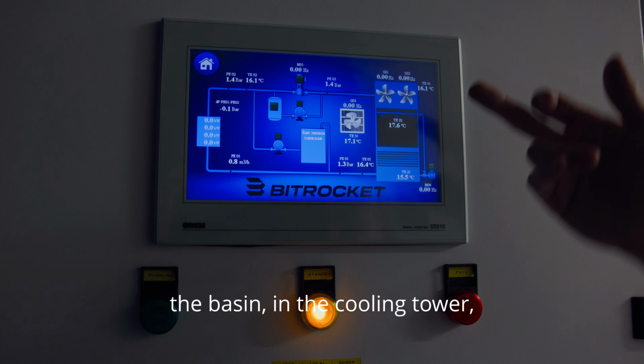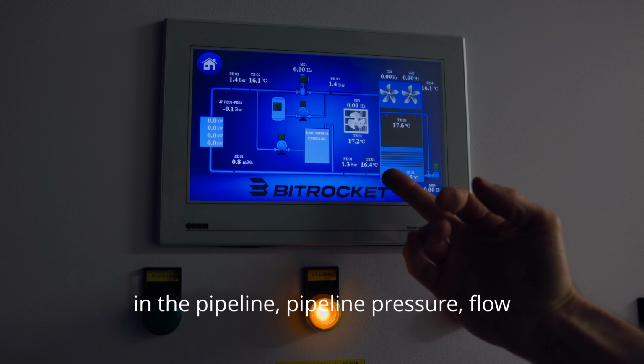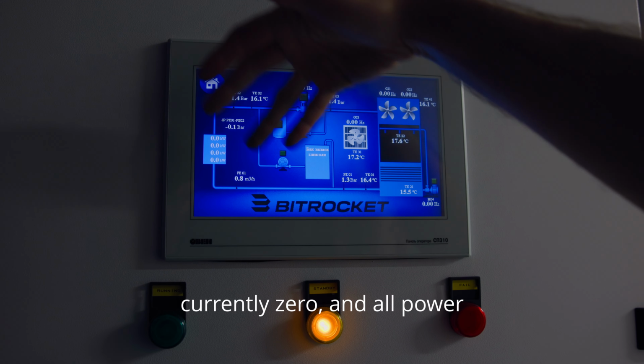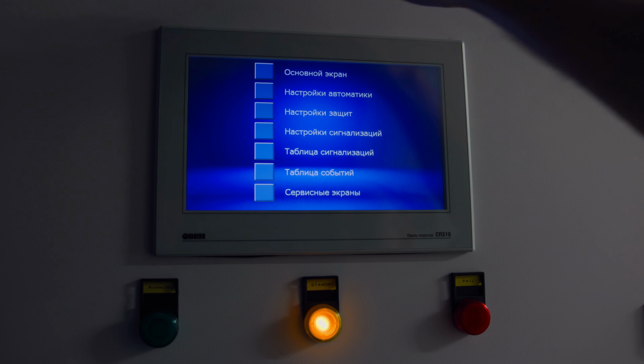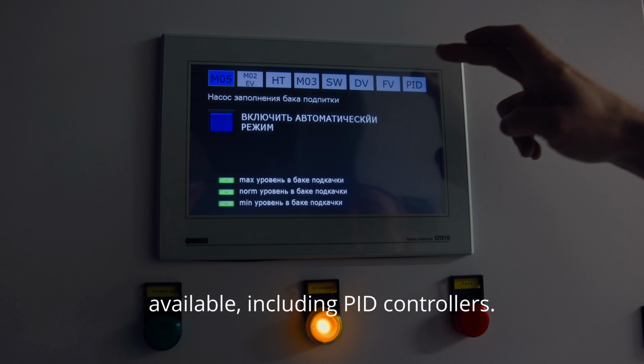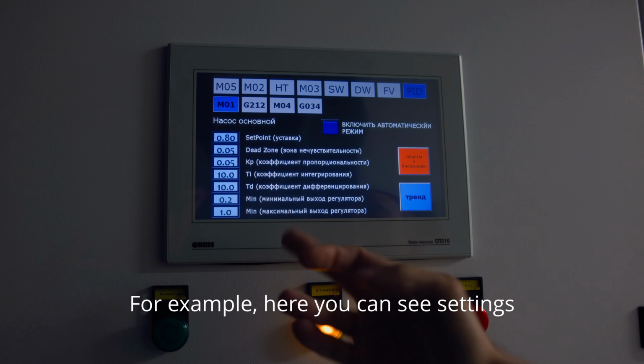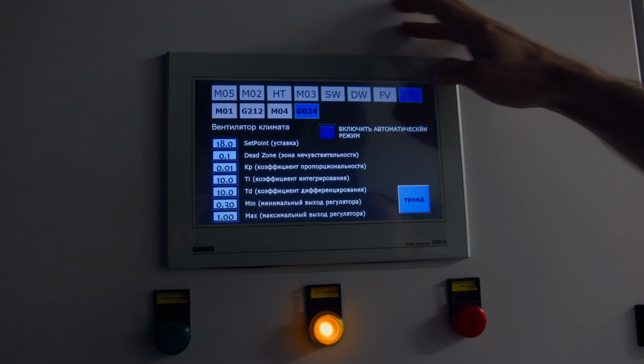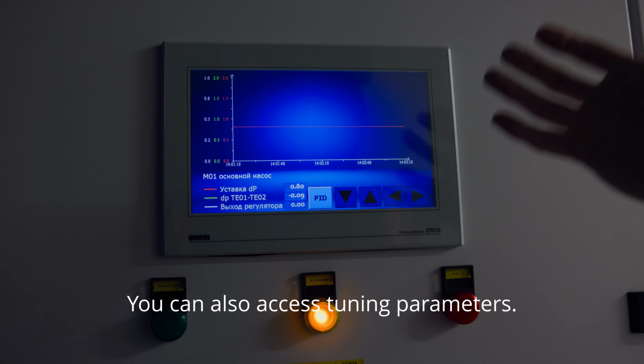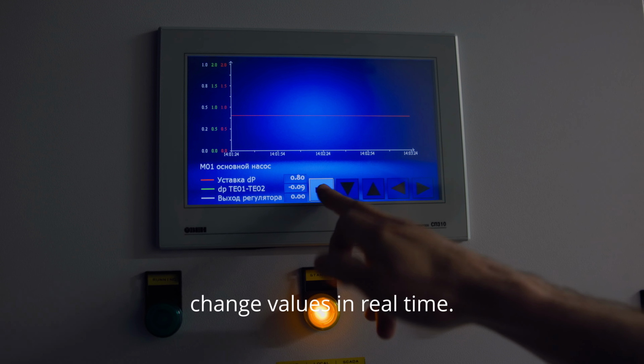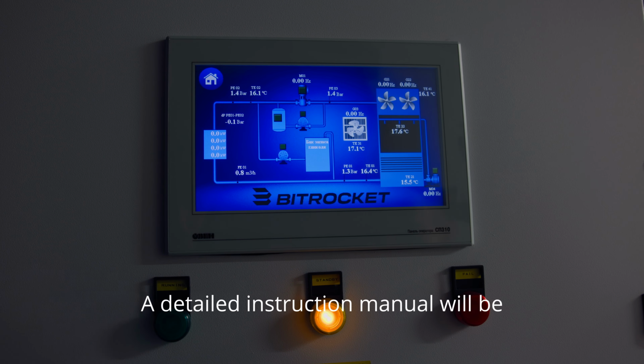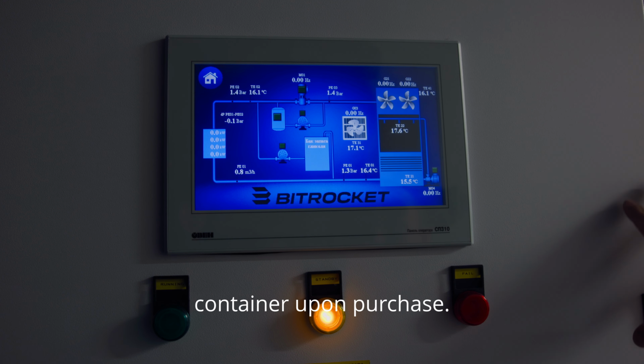This is the main control interface. Here we see the temperature outdoors, in the basin, in the cooling tower, the pipeline pressure, the flow rate, which is currently 0, and all power readings and other key parameters. There are many configuration menus available, including PID controllers. For example, here you can see settings for the main pump, cooling tower pump, spray pump, and internal pumps. You can also access tuning parameters. When adjusting a PID controller, you can change values in real time. A detailed instruction manual will be provided with the container upon purchase.